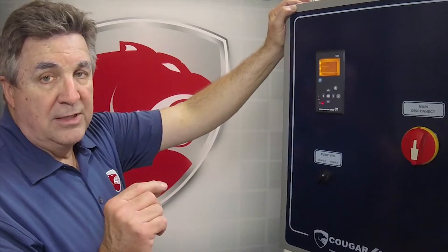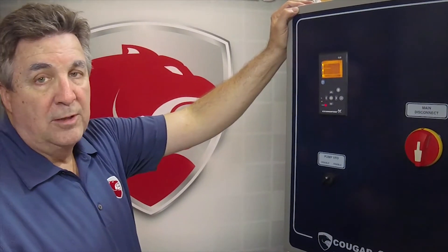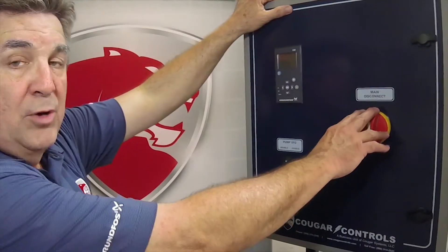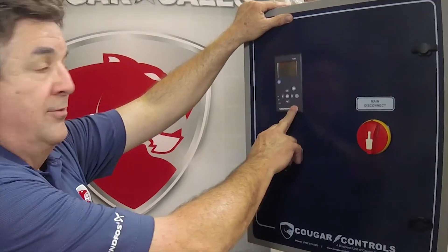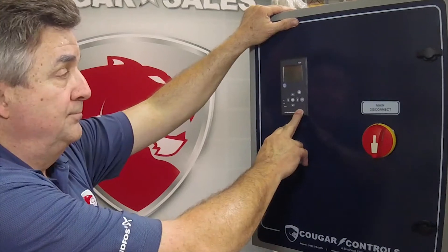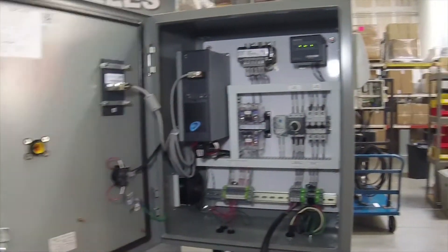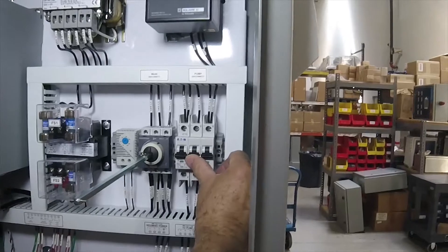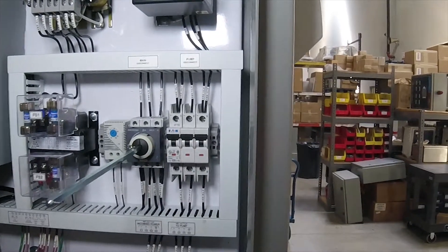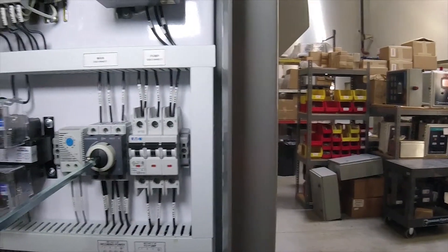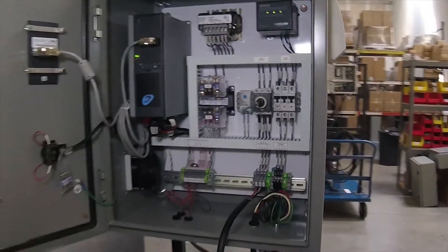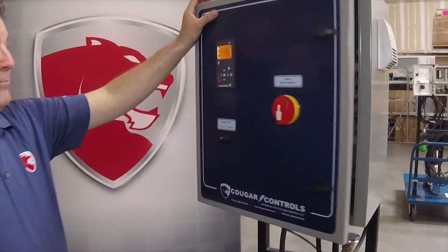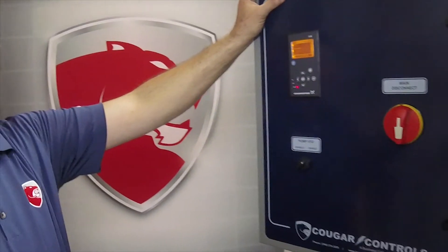Just a quick note: if you turn the breaker on and the drive doesn't appear to power up, check on the inside and make sure that this breaker is flipped up. That's just circuit protection for the drive. It could have been off or tripped. Once you get that back up, you'll have power to the drive.